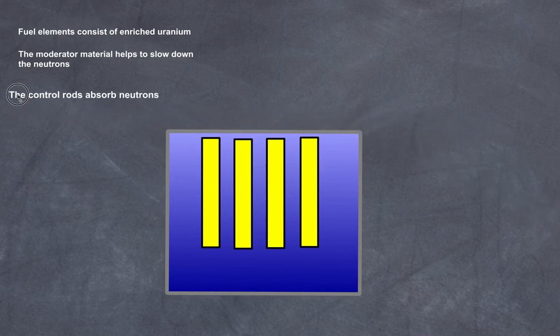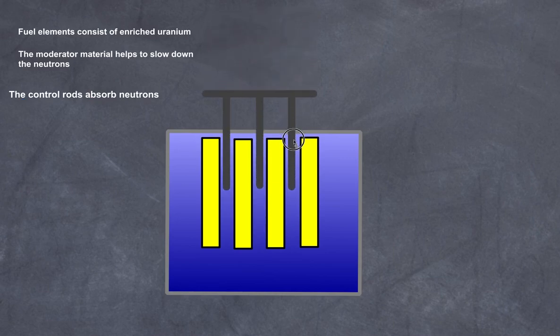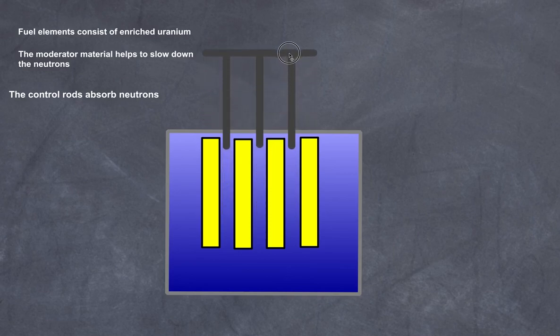The third component is what we call control rods. Control rods don't slow my neutrons down, they absorb neutrons. They're usually made up of a material that is poisonous to neutrons. In other words, it absorbs neutrons and won't let them go. The control rod allows us to control the rate of nuclear fission. By removing the rods, we increase the opportunity for neutrons to continue the fission process. By introducing my rods, I'm absorbing neutrons, taking them away from the uranium-235, and therefore lowering the K value. And thereby we can actually slow the reaction or even completely stop it down. One of the most common safety features in a nuclear reactor is simply a device that throws the rods down straight into the core, which stops the reaction in its tracks.